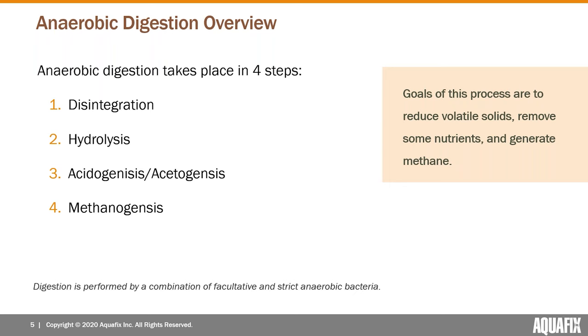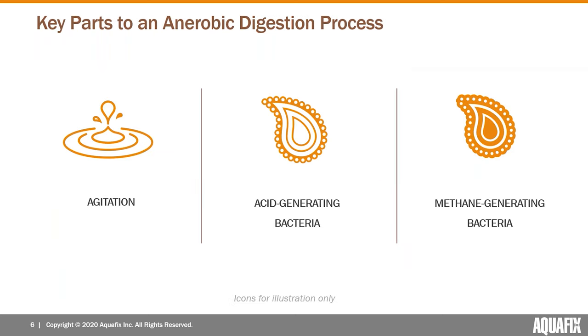After disintegration you have acetogenesis, converting long-chain fatty acids into short-chain fatty acids like acetic acid and then into acetate specifically. Then you have methanogenesis, which is the most finicky point of anaerobic digestion. The methanogens require the most specific conditions and there aren't many different methanogens present. The acid-generating bacteria convert everything into acetate, and then the methane-generating bacteria produce methane primarily from acetate.